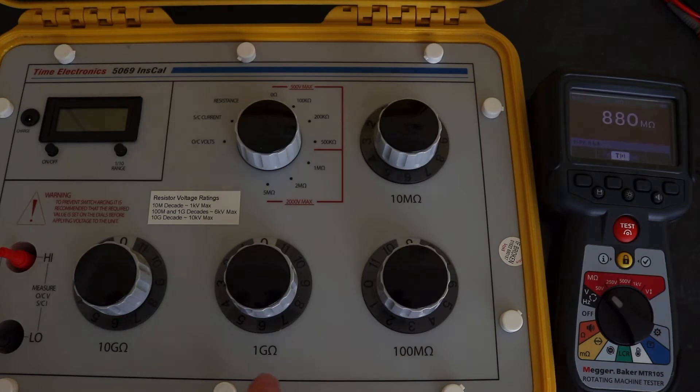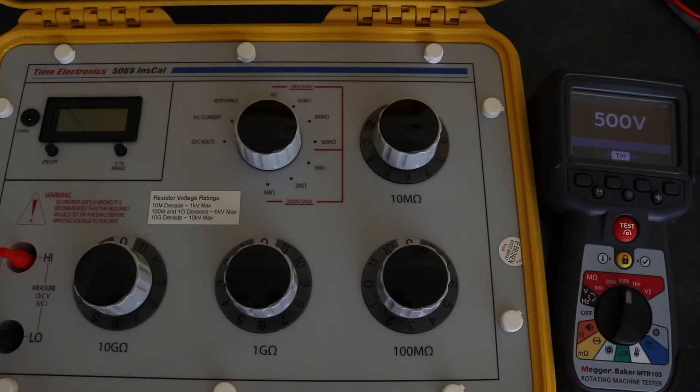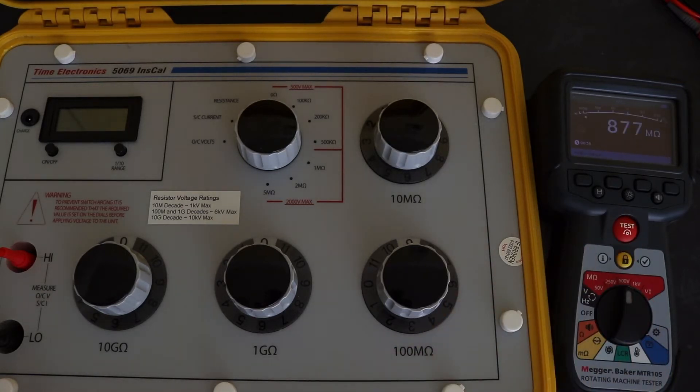Knock him off and I'll fling him around to 500 volts. Press the go button again and you can immediately see I'm now up to 893 mega ohms there.